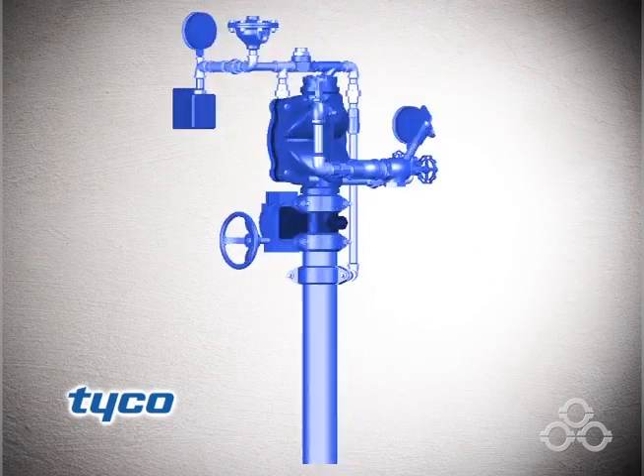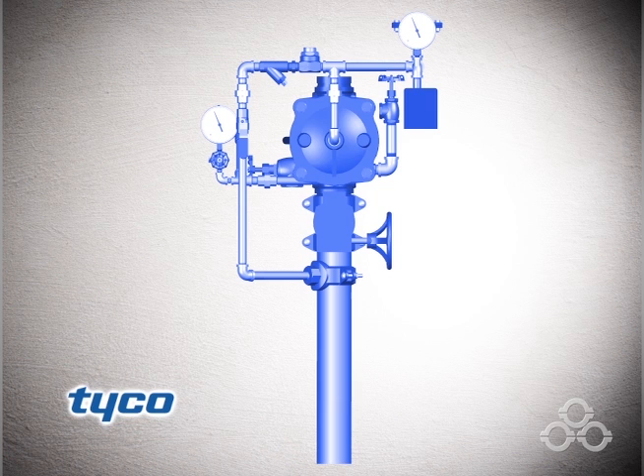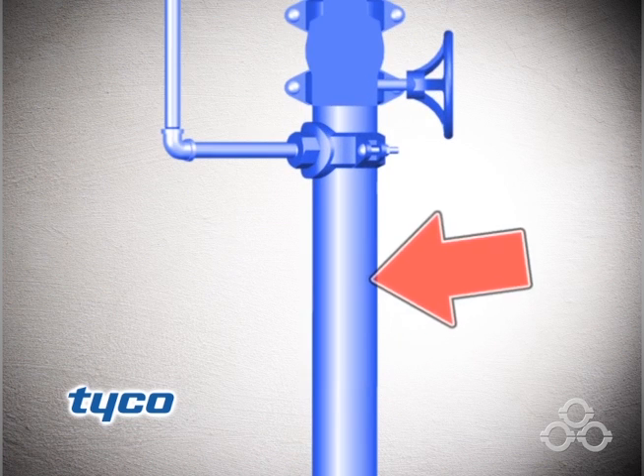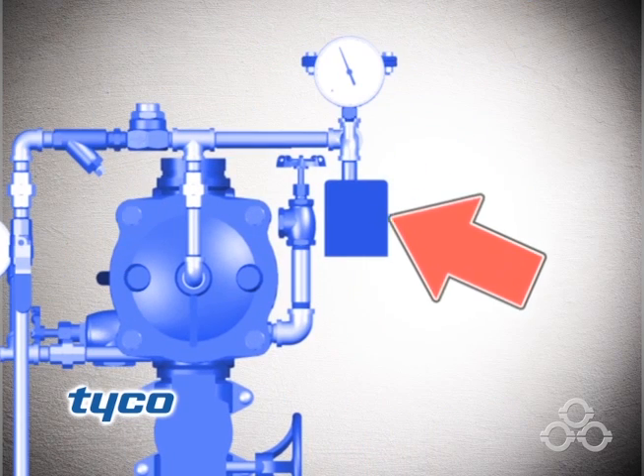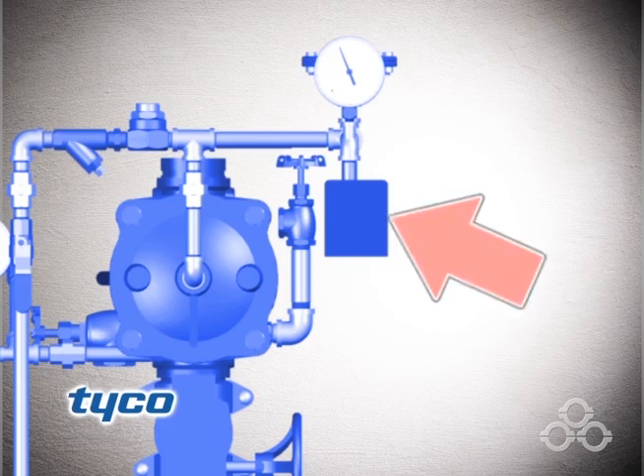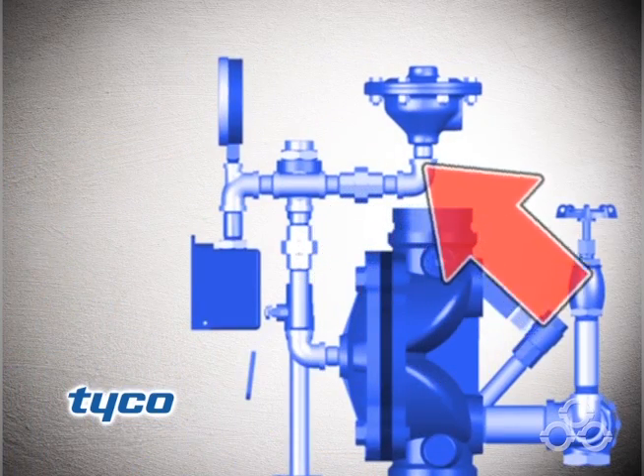The system supply contains water under pressure, shown here in blue. In the set condition, water supply pressure is applied to the DV-5 waterway inlet, the DV-5 diaphragm chamber, the Model MC-1 manual control station, and inlet of the Model DP-1 Dry Pilot Actuator.